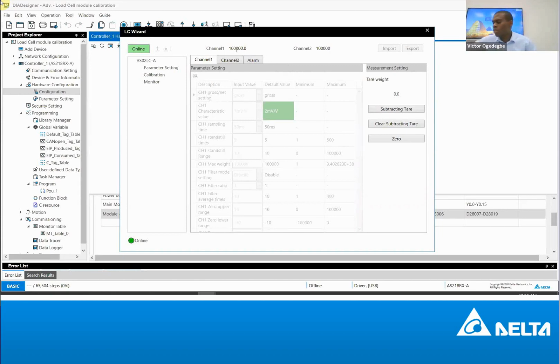When I configure it, if I apply some load on my sensor, it can read some value. Yeah, you can see some value already. This is just like raw data from the sensor. Later on, before we bring this meeting to a close, we'll look shortly at calibration. The essence of calibration is to make what you measure have a correct digital value. Digital values are the values you have in those registers I showed you, and based on that digital value, you can now work in your application.